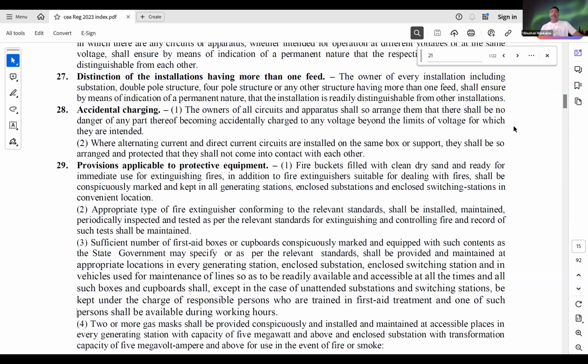The second part comes in Regulation 29, where provisions at the substation level are also elaborated. And I must say, wherever I have seen in Mumbai and around, these basic things are missed out. Let me read out a few important words in this regulation which are missed out: fire buckets filled with clean, dry sand. I just struggle to find clean, dry sand in these fire buckets. There are fire buckets provided near the substation, located at a very conspicuous location, wonderfully placed, but there's no dry sand. So in case of emergency, the wet sand will not provide the adequate protection that is required.